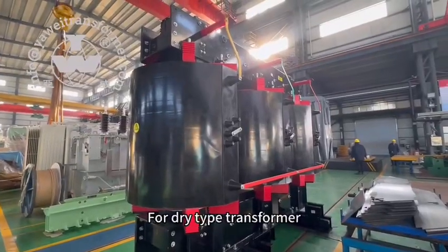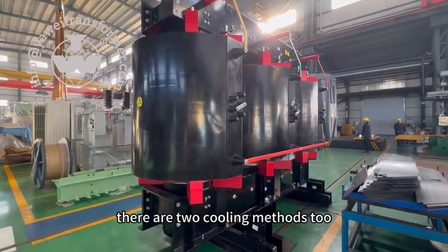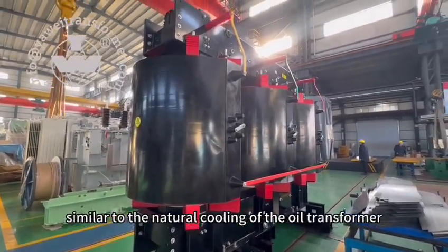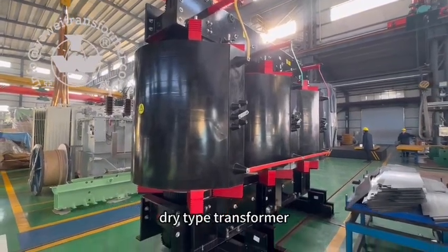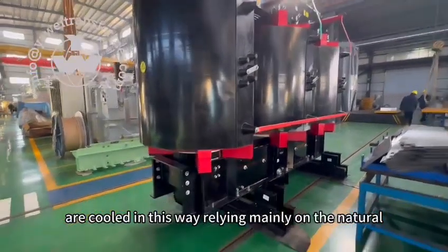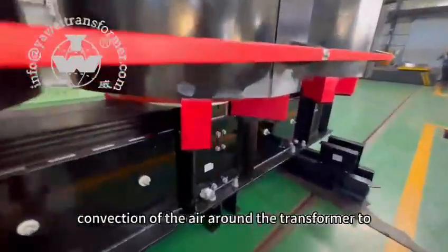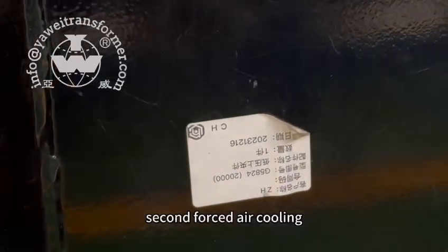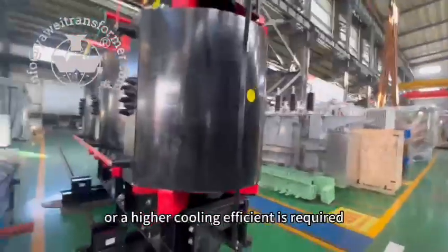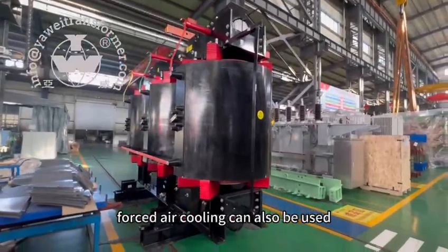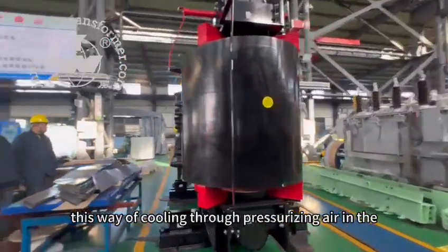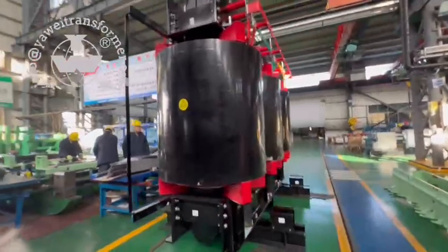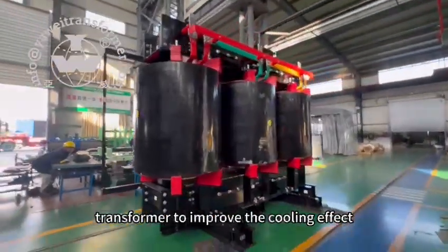For dry type transformer, there are two cooling methods too. One is natural cooling, similar to the natural cooling of the oil transformer, relying mainly on the natural convection of the air around the transformer to dissipate heat. Second, forced air cooling. When the capacity of the dry type transformer increases or higher cooling efficiency is required, forced air cooling can also be used. This way of cooling works by pressurizing air in the transformer to improve the cooling effect.